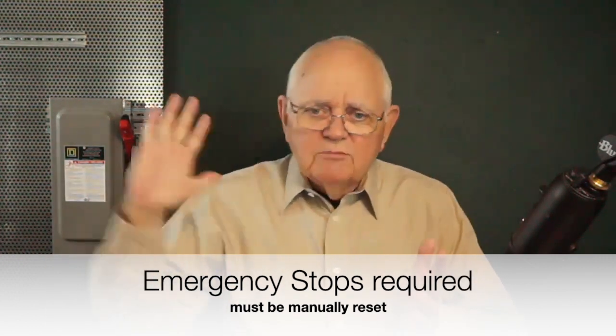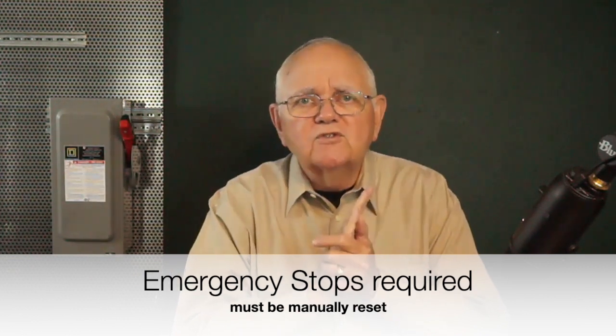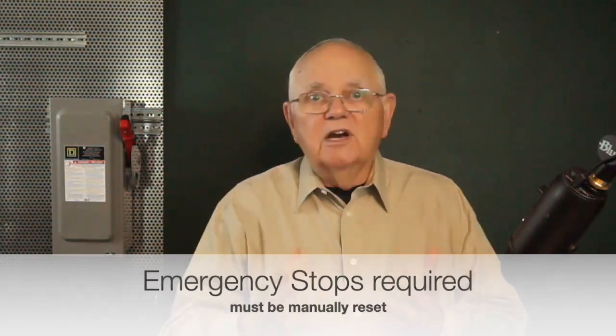Now, when I push that emergency stop in, that big red mushroom head, it stays in, it doesn't come back out. It keeps the contacts open that are preventing my machine from running. Therefore, in order to close those contacts, I've got to go back up to that stop push button, rotate it a quarter or half turn or whatever, and allow it to pop back out.